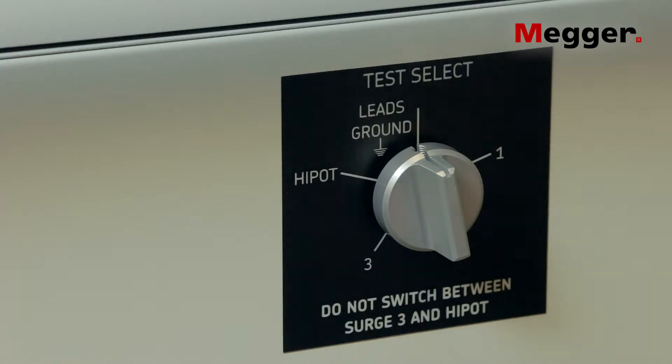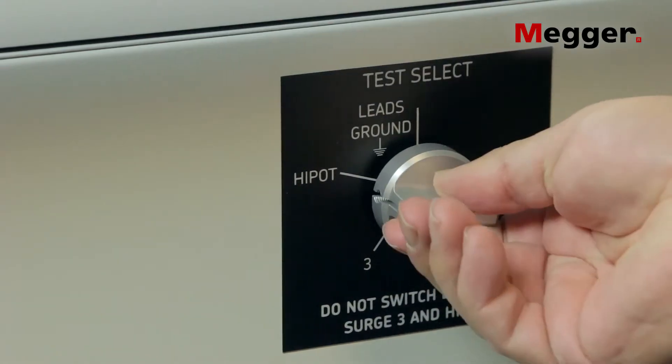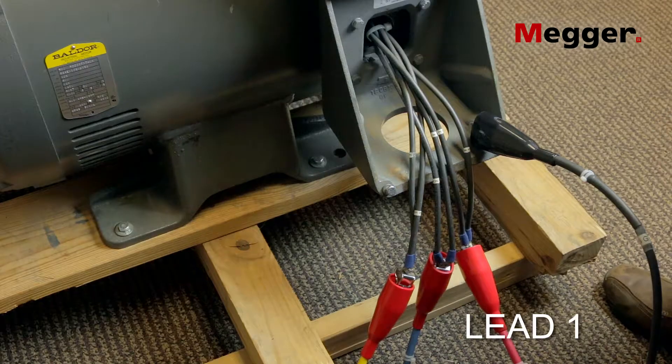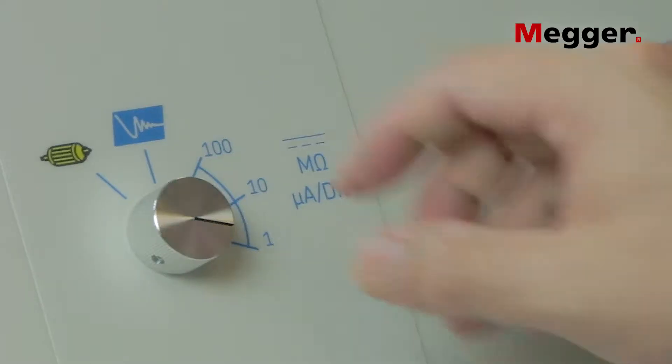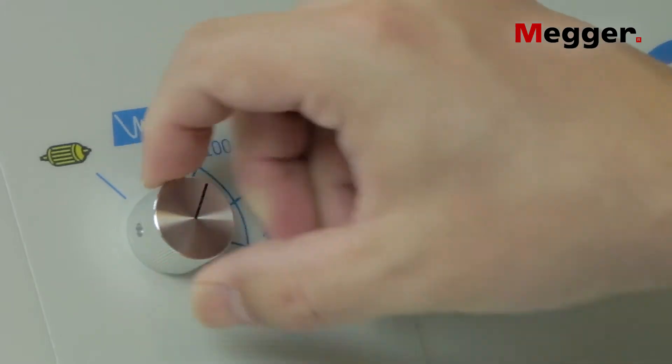Turn the test selector switch to the high pot position. It is important to note that only lead one will be energized during the high pot test. Turn the power pack's function switch to the 100 microamps per division position.